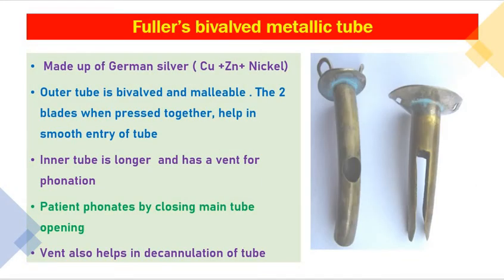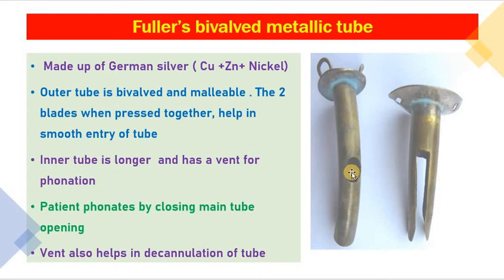Next is Fuller's bivalved metallic tracheostomy tube, made of German silver containing copper, zinc, and nickel. It is more malleable than Jackson's metallic tube. The two blades, when pressed together, allow smooth entry without requiring a separate obturator. The inner tube is longer and has a vent for phonation — which is lacking in Jackson's tube. When the patient closes the main tube opening, they can phonate. The vent also helps in decannulation: the outer part of the tube is closed and the patient breathes toward the larynx and through the nose.